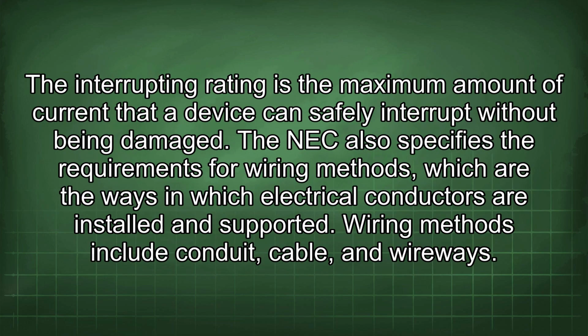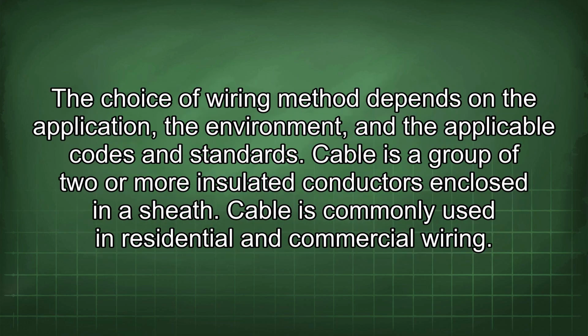The interrupting rating is the maximum amount of current that a device can safely interrupt without being damaged. The NEC also specifies the requirements for wiring methods, which are the ways in which electrical conductors are installed and supported. Wiring methods include conduit, cable, and wireways. The choice of wiring method depends on the application, the environment, and the applicable codes and standards.